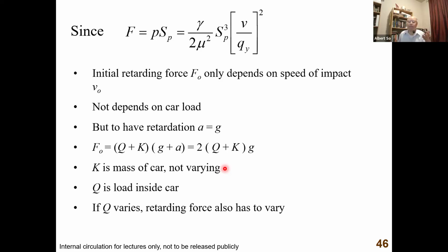So it's very dangerous. So that's why the regulations say, under all circumstances, whenever the car is being braked, either by the brake or by the safety gear or by the buffers, the deceleration must not go beyond g. That means your feet should only need to withstand 2 times your weight.